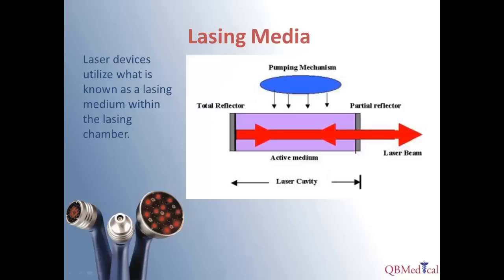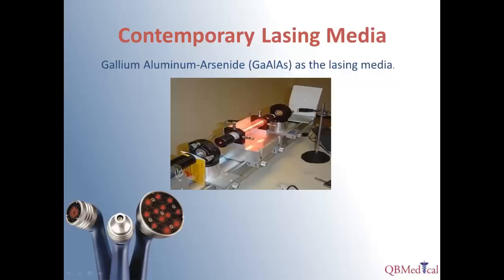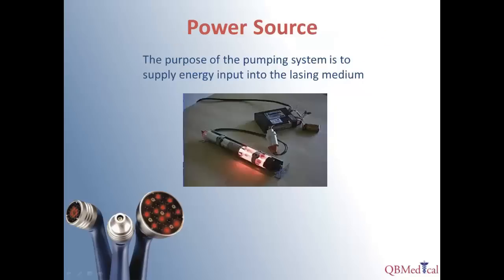Within the lasing chamber, we have what is referred to as a lasing medium. When power is input to the chamber, the molecules of the lasing medium become stimulated, which is what allows for amplification. Contemporary lasers can be built with a variety of lasing mediums; gallium aluminum arsenide is a commonly seen lasing medium used in therapeutic lasers. The power source is the component of the laser that actually provides energy into the system.